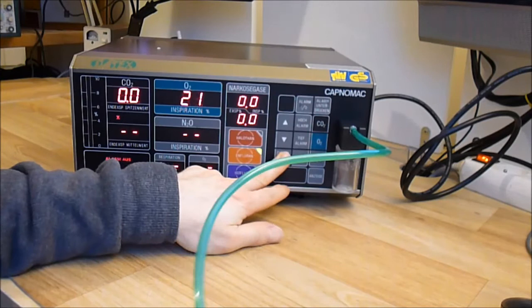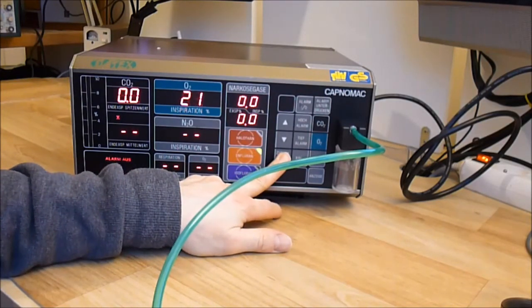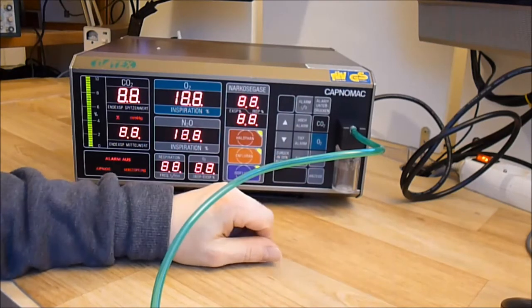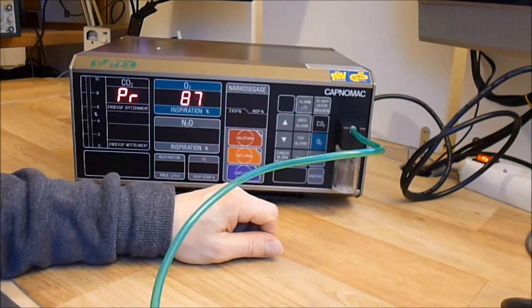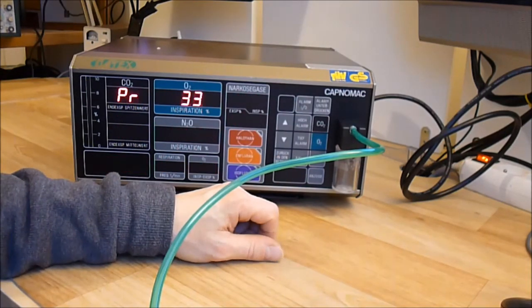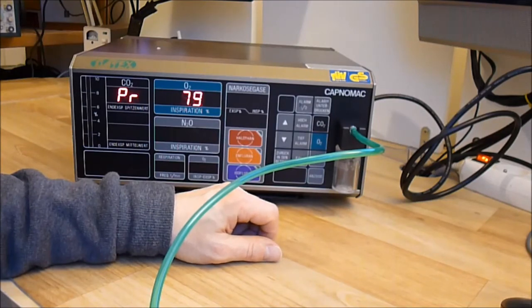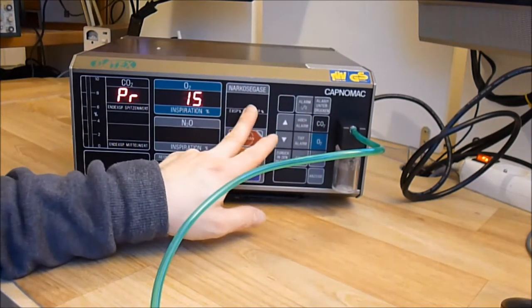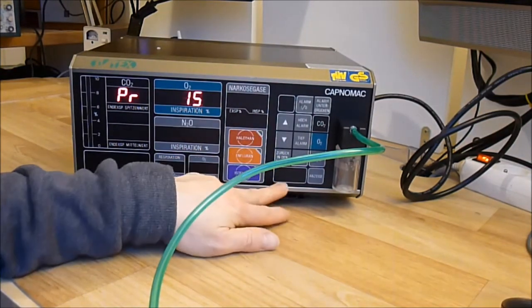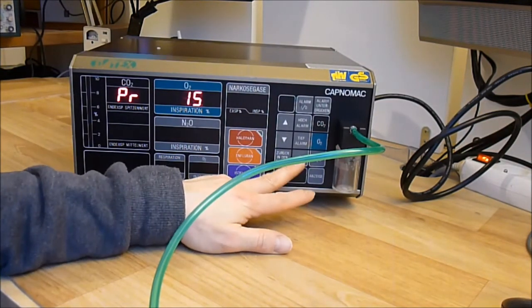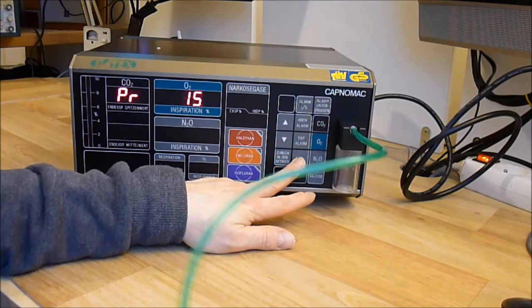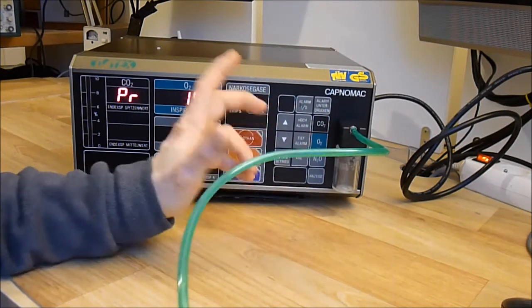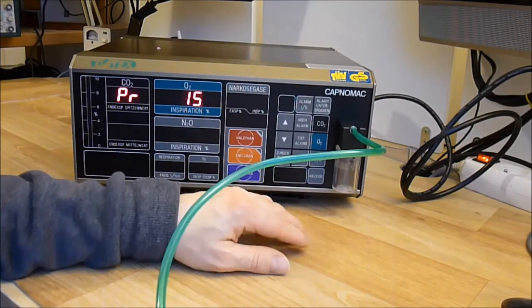So if I press this button, it will reset. And it is doing its boot process again. So these keys are for setting the alarm levels. And there is a calibration procedure for it, but it requires calibrated gas to do it, a can of gas, so I cannot do it anyway.